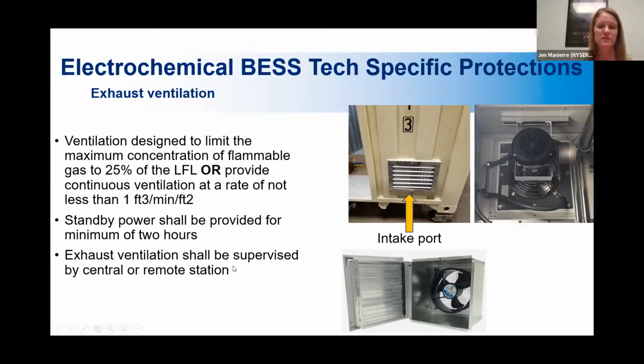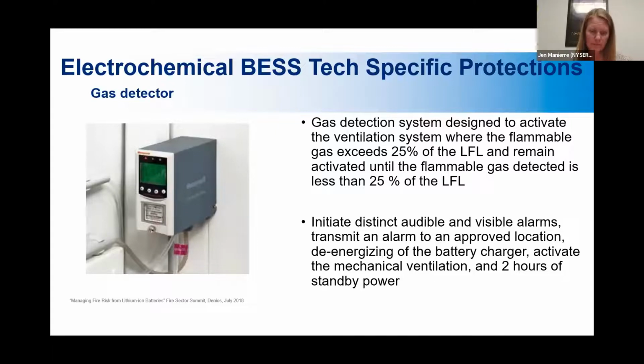And the exhaust ventilation, just like the rest of the system, needs to be supervised by a central or remote station. It would be the same one that the battery management system is connected to, where it's going to send alert signals if anything goes wrong. Similarly, there needs to be a gas detector in there to be able to trigger that ventilation system, right? And also transmit audible and visible alarms to an approved location. You don't want any of these alarms just going off in the place where the batteries are, because many of these systems are not going to have humans around them at all times. So anytime there's an alarm, it should be going to some approved central location, likely elsewhere.